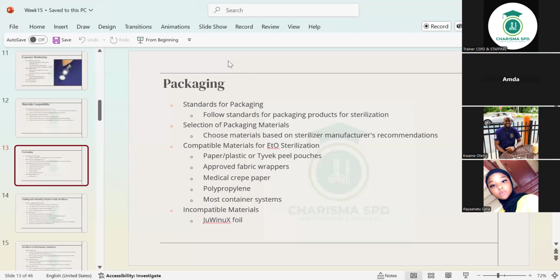And then most container systems. When you go to the hospital, the facility, you're going to see a lot of our canisters. We call them canisters, and they have other containers too from different materials. So the ETO sterilizer takes most of these container systems. Things that are incompatible: the JuWinuX foil. It's very technical, but it's a foil. Even our microwaves at home don't take foil. So you see that foil is going to be a problem in a low temperature sterilization process. I've not come across it. I've not seen one myself because we don't use the ETO at my facility. But in case you see it where you're going, it's a no-no for ETO sterilization.